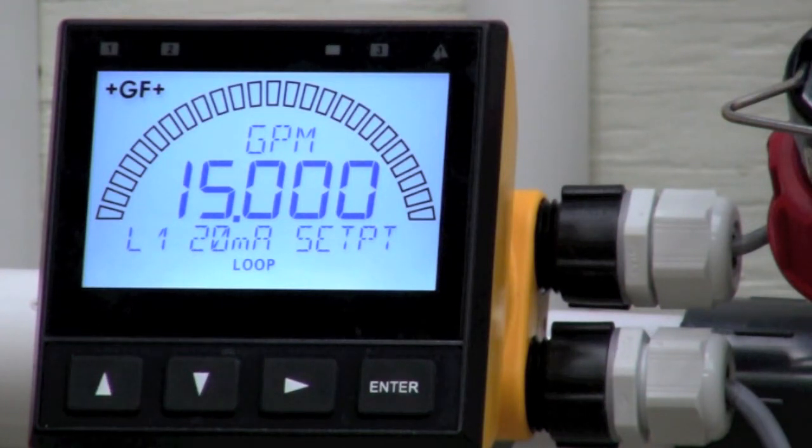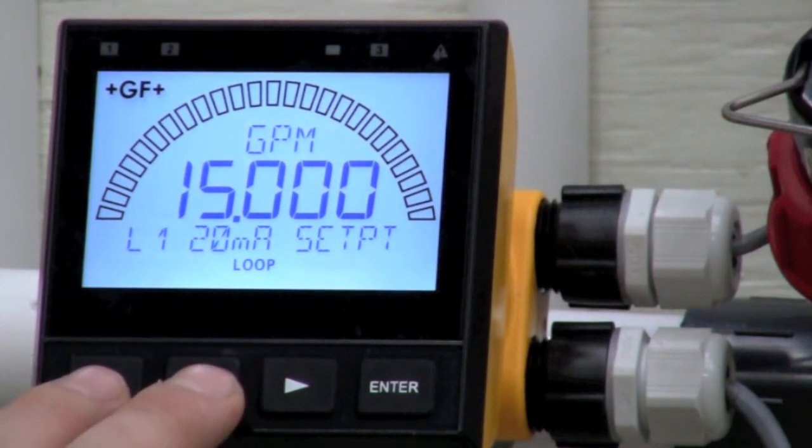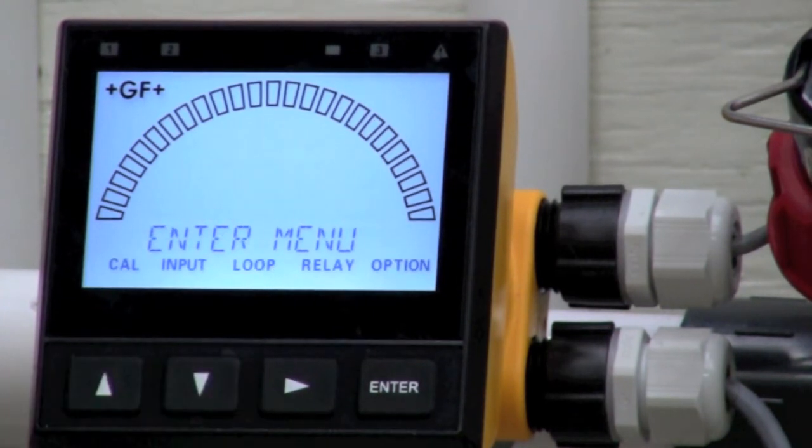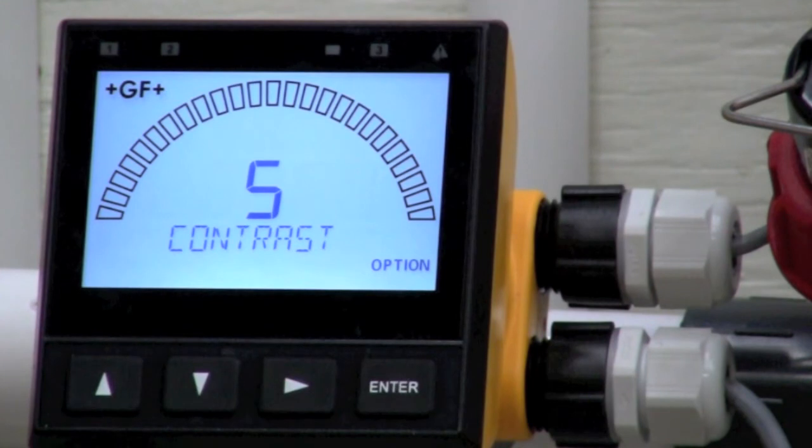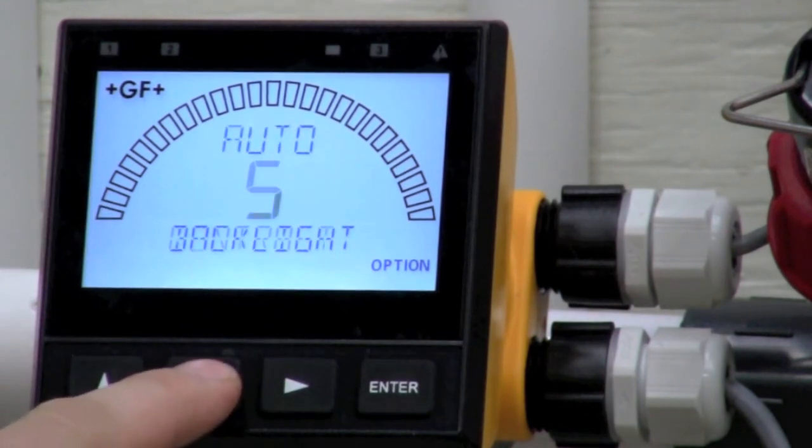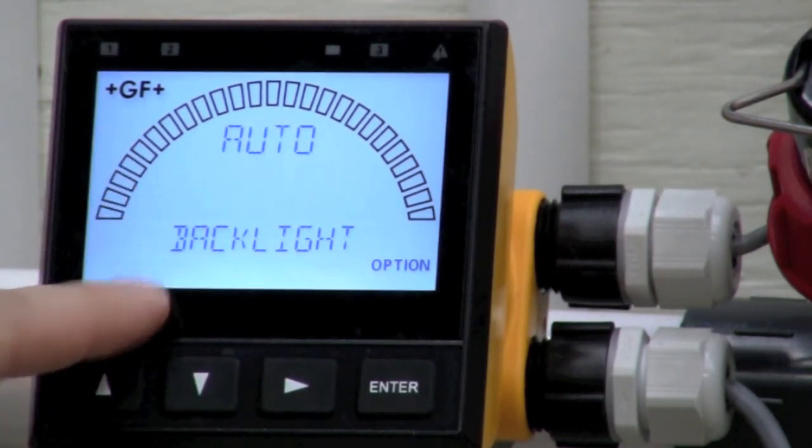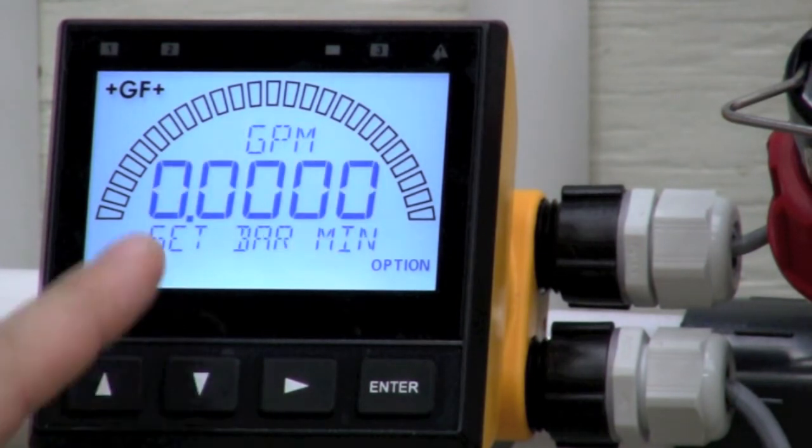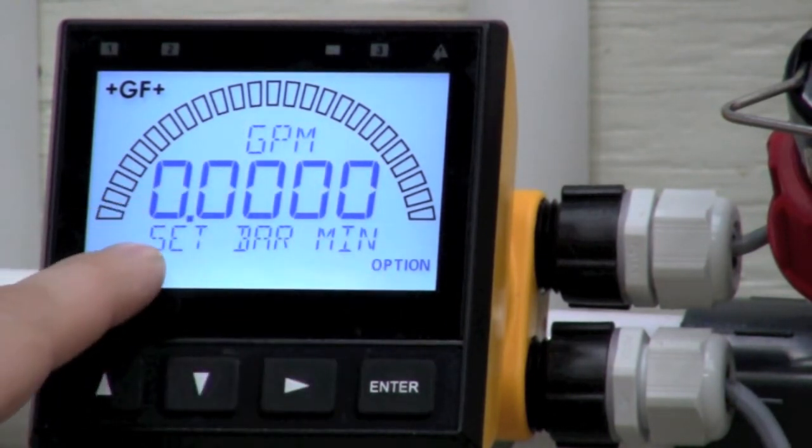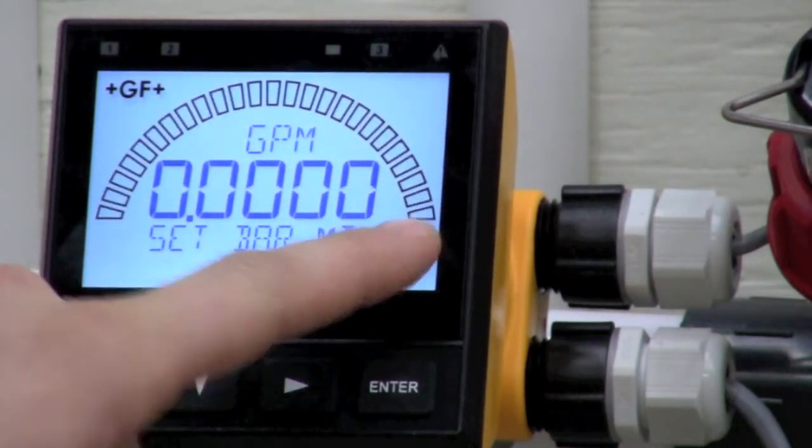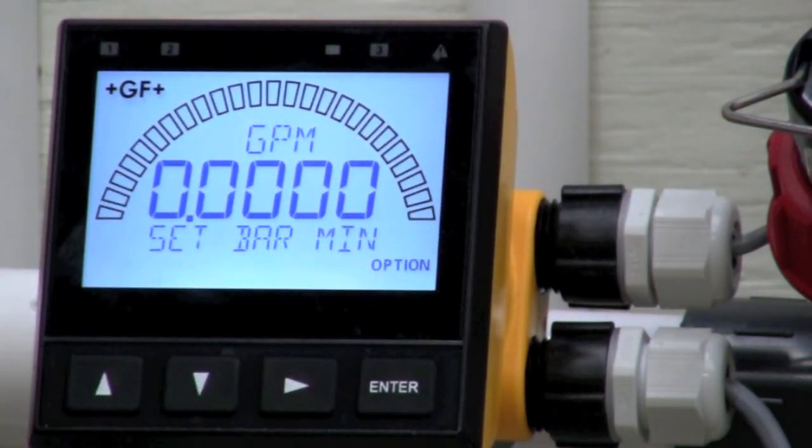There's a couple other niceties that you can go into that a lot of people like to set. I'm going to show you those real quick. I'm going to back up both buttons. If I go over to options, hit enter. I can adjust the contrast here if I so desire. Backlight, I'm going to leave that on auto. This is for the bar graph. You see this bar graph here. This operates independently of the 4 to 20 milliamp output. What you put here does not affect it and vice versa.